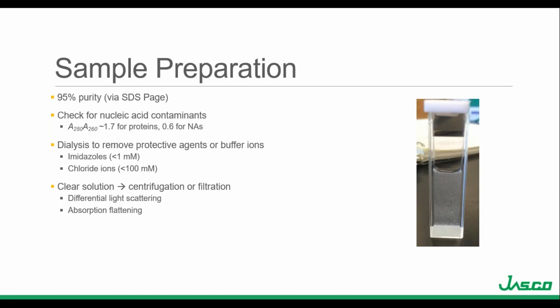Dialysis can be used to remove protective agents or buffer ion contaminants. Imidazole and chloride ions pose issues to good CD data since both have strong absorbance in the far UV, reducing signal to noise. Imidazole concentrations should be kept under 1 millimolar, and chloride concentration below 100 millimolar, although lower is better. The protein solution should also be clear or transparent to avoid artifacts in the CD spectrum, achieved through ultracentrifugation or filtration. The figure on the right shows a protein sample that aggregated, with white particulates and a cloudy solution — that's what we want to avoid.